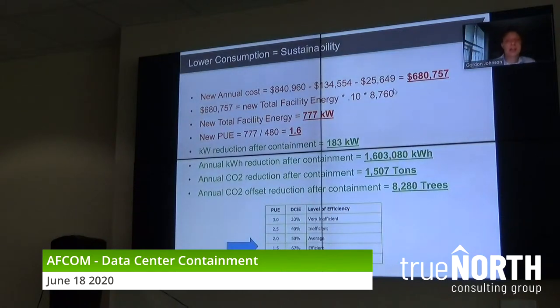Getting back to this data center, we have a new annual cost. We dropped it down from $840,000 to $680,000, highlighted, underlined. My new facility energy dropped to 777 kW. My new PUE is 1.6. If you look at that chart, I was an average 2.0 PUE data center. I'm bordering on an efficient data center at 1.5.